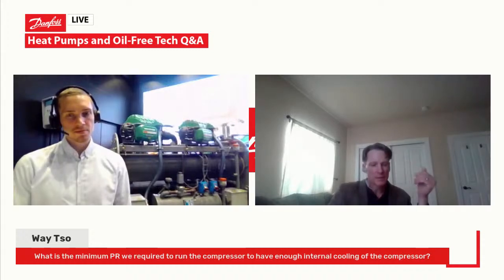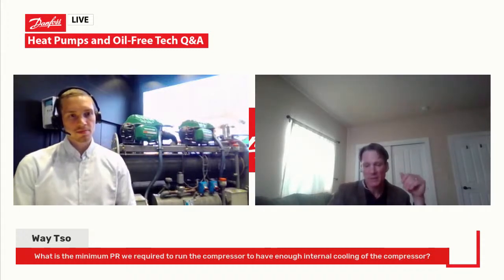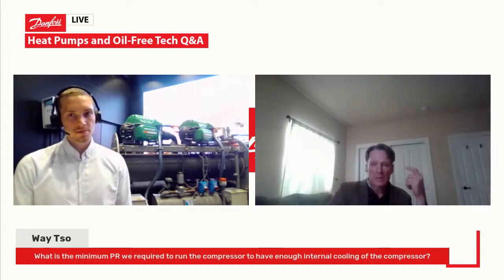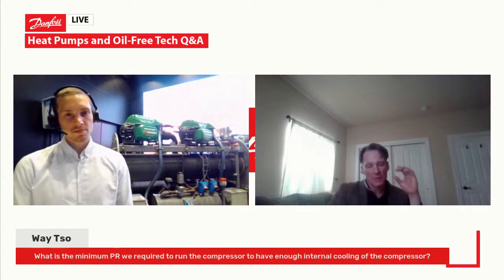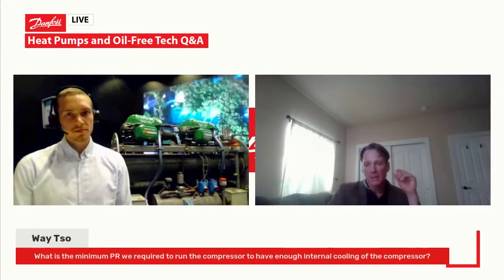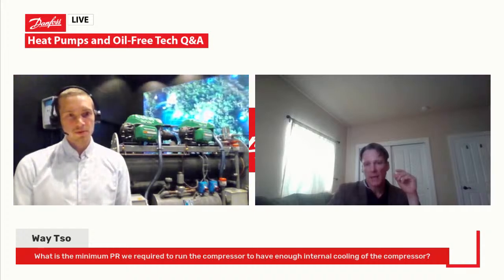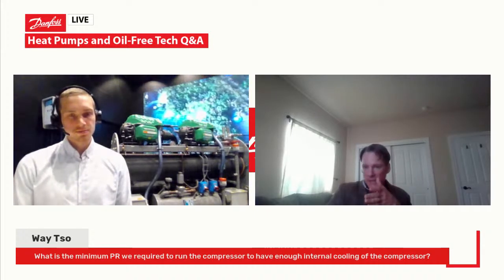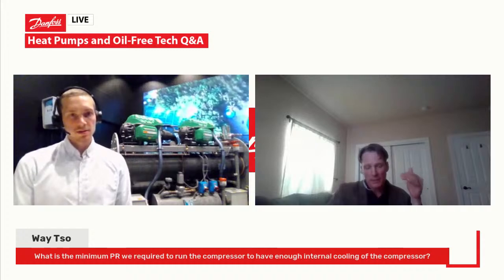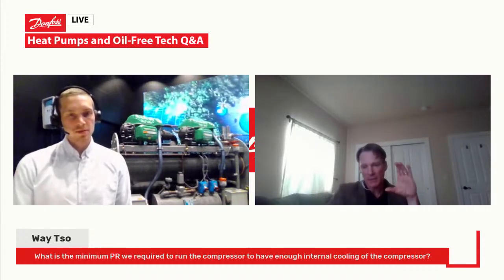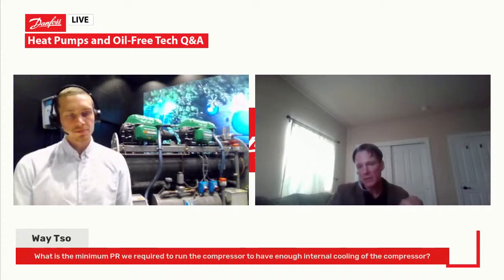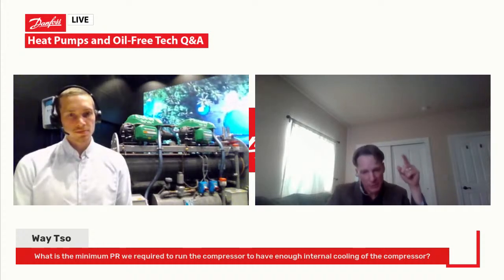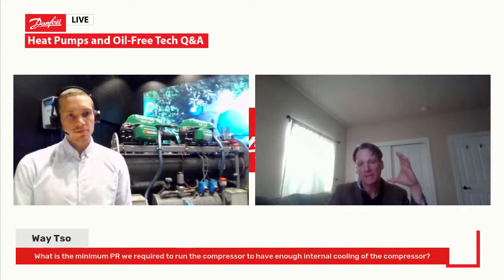And you can raise the temperature at least to normal sensible cooling load chilling levels, which is around 15 degrees Celsius. But data centers have figured out that CPUs actually can reliably operate at much higher. And the reason our technology has become so prevalent in those applications is because of the low lift, or low differential temperature and pressure benefit of the operation of that technology. So an oiled system, and it ties back to the oil versus oil free. In an oiled system, you have to have a certain amount of differential pressure and temperature to return the oil back to the compressor. If you have no oil, you don't have that limitation anymore.